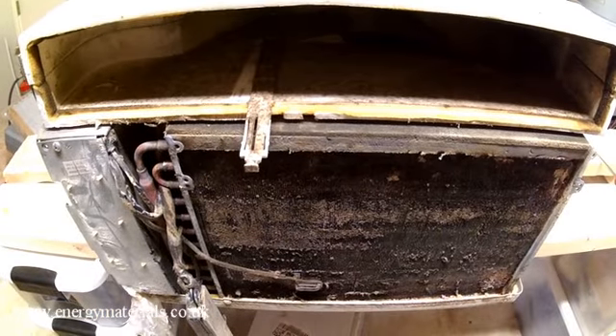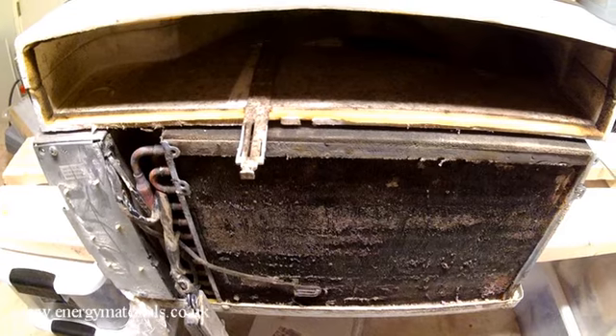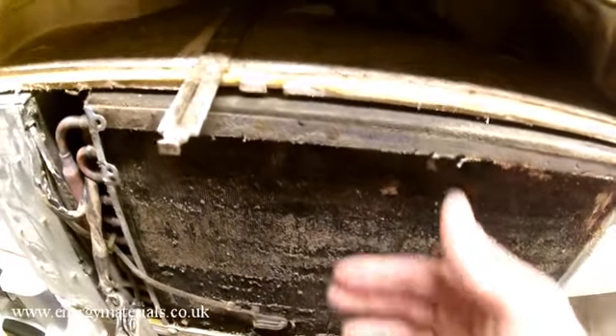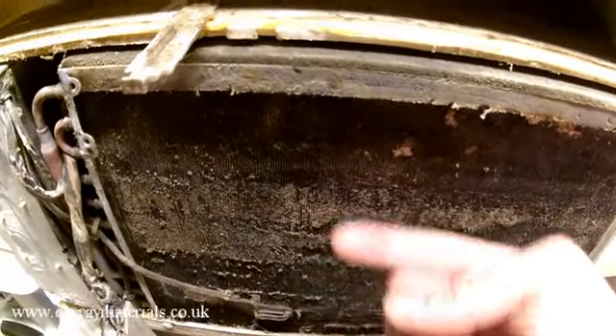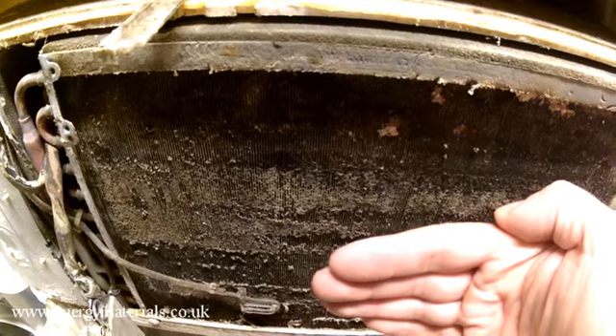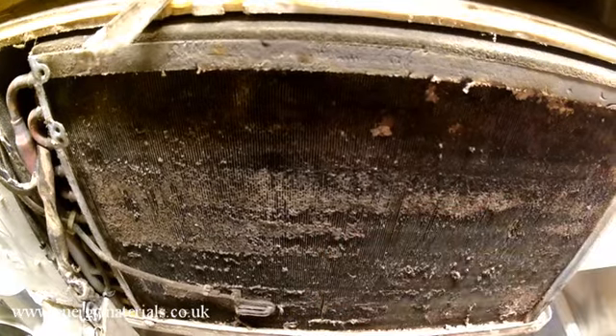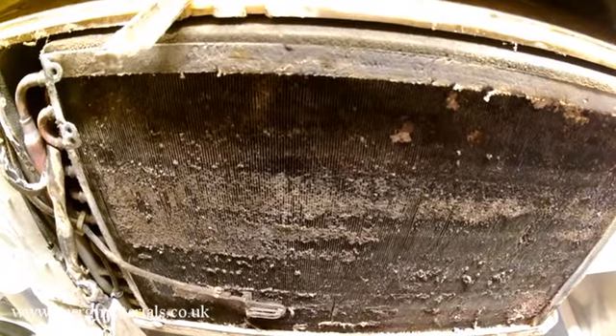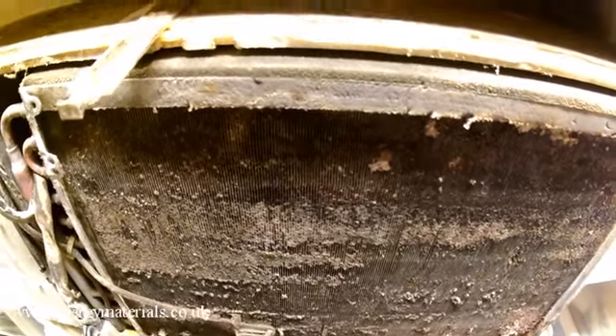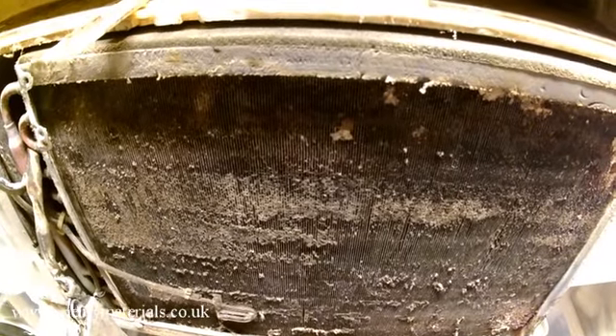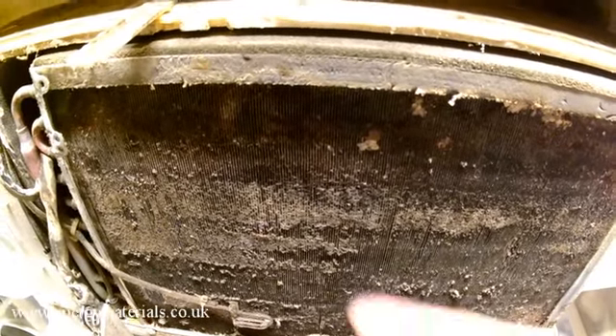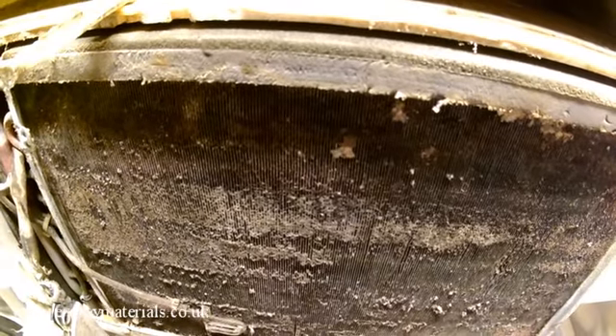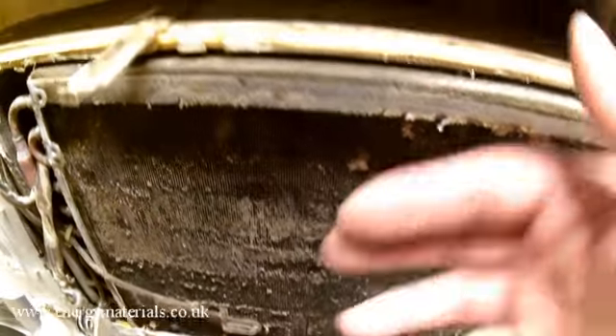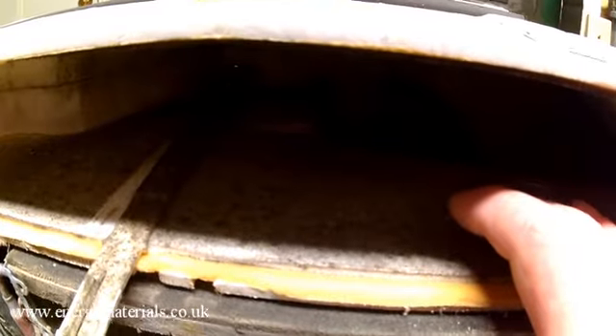So here is our window AC unit with the outer cover removed. We can see in the evaporator at the front, we can see a lot of dirt. Originally there was a filter in the front of this. Either this unit was run without the filter for a period of time, the filter was ineffective, or the preventative maintenance was not carried out for filter replacements. But we can see a lot of dirt on the front, so this is really not good news, and this will have to be cleaned. So air would have gone in, and then this is the ductwork which returned it back into the room. So let's have a look.